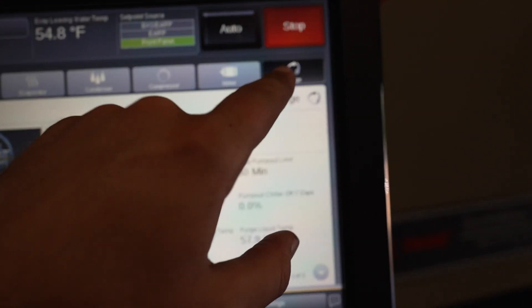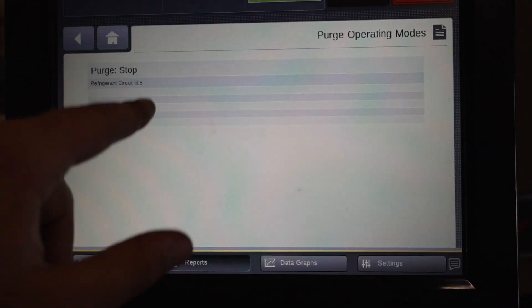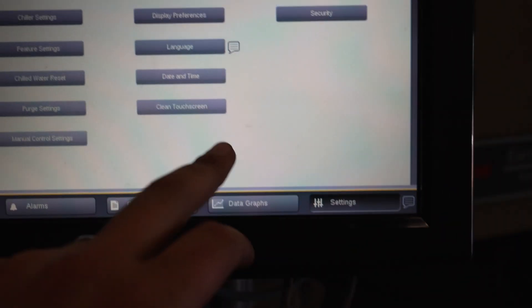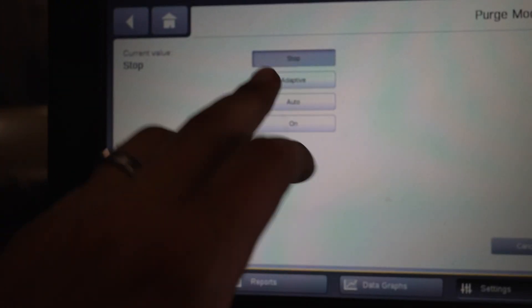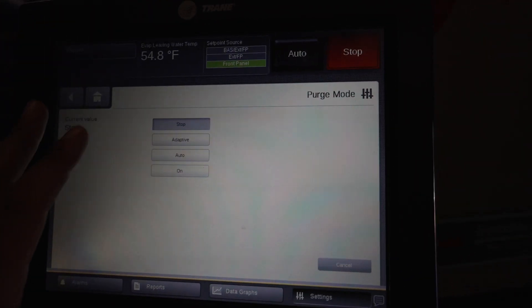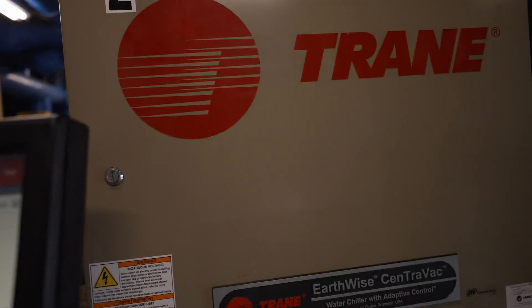Make sure you come over here to the purge menu. The chiller has to be off and shut down, and make sure you put the purge into a stop cycle. You can do that over here via settings, under purge settings, and make sure we're in a stop mode. Now if you're in the UCP2 series controllers, you will have a setting in the control panel where you can go under the purge menu and set it to off.